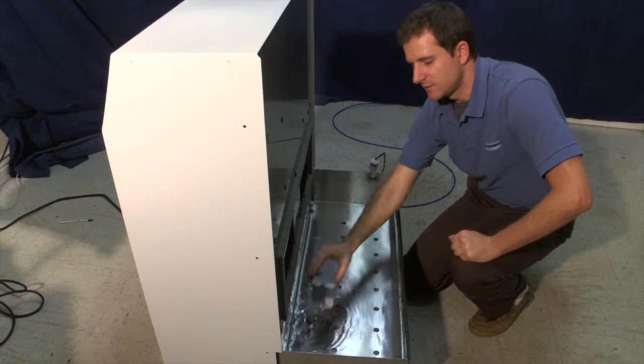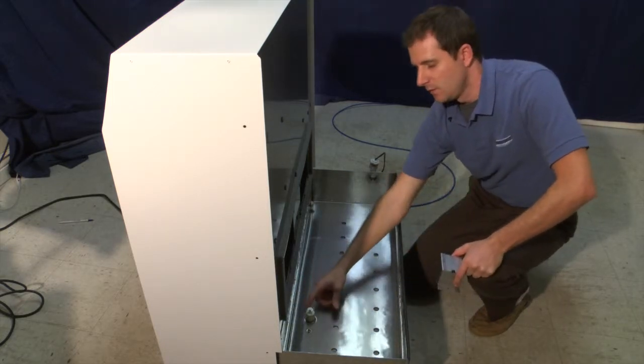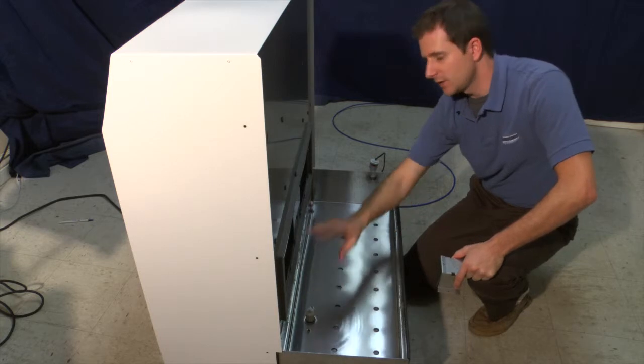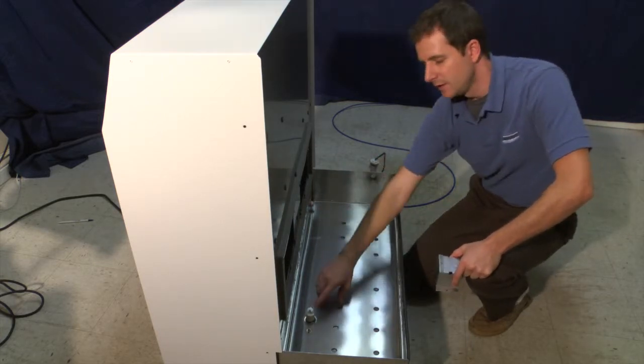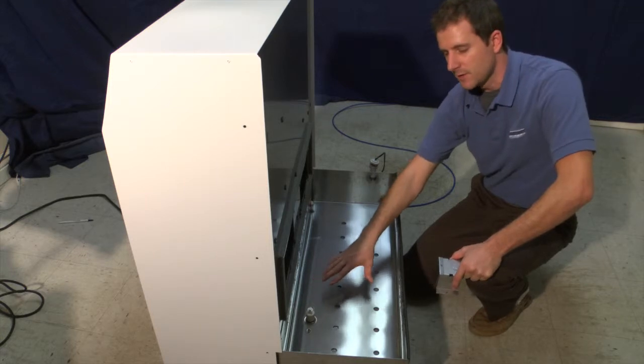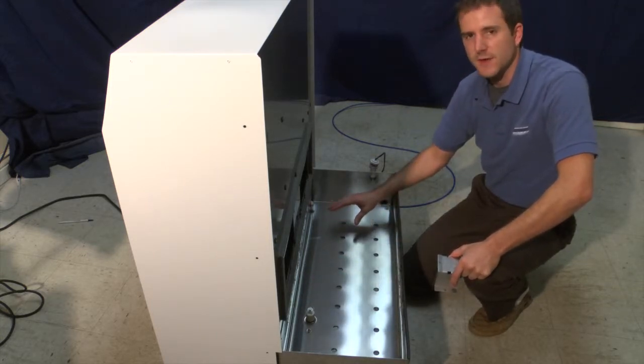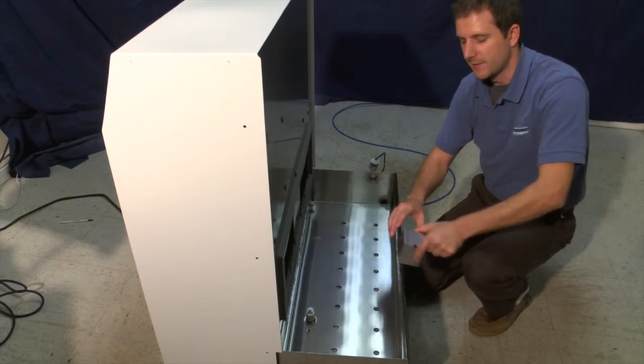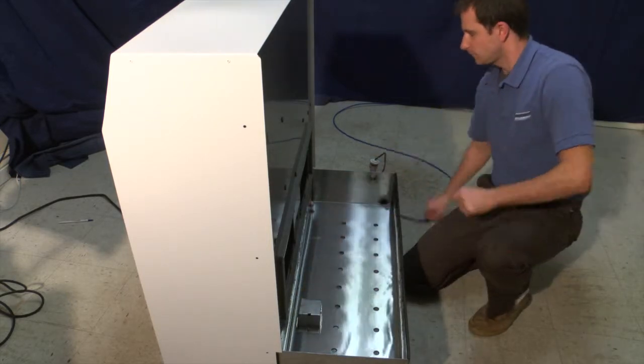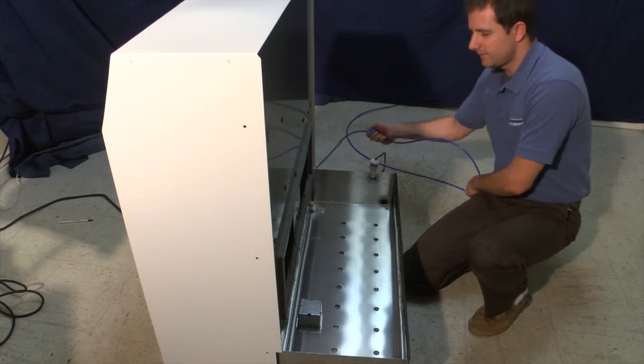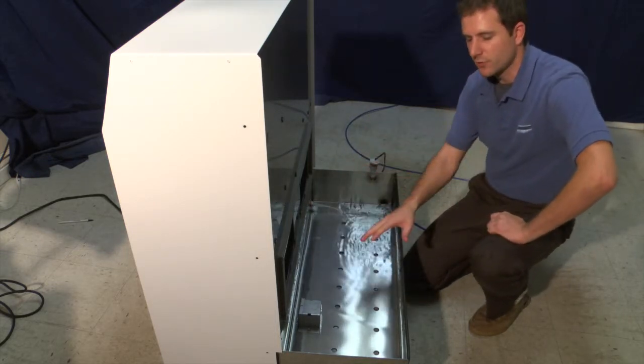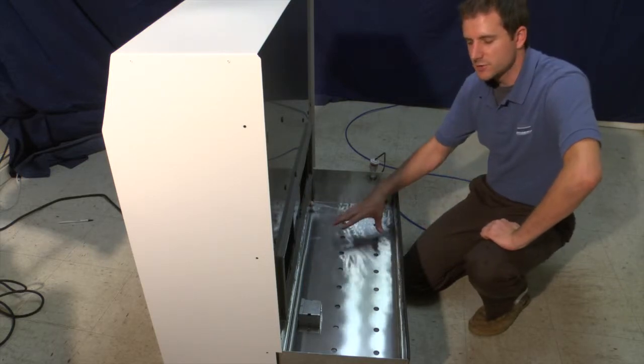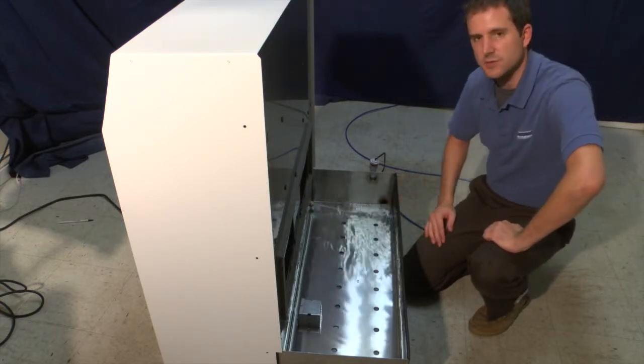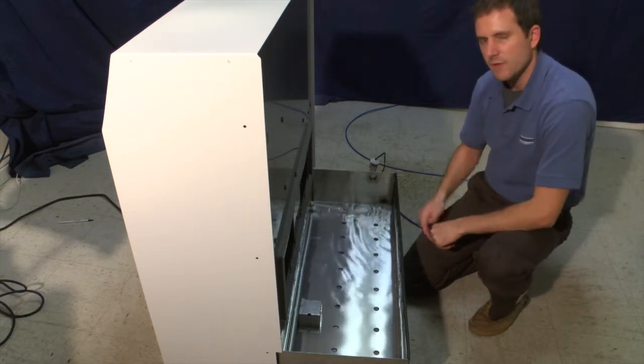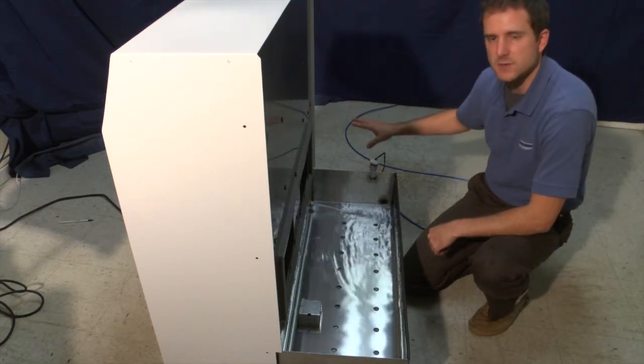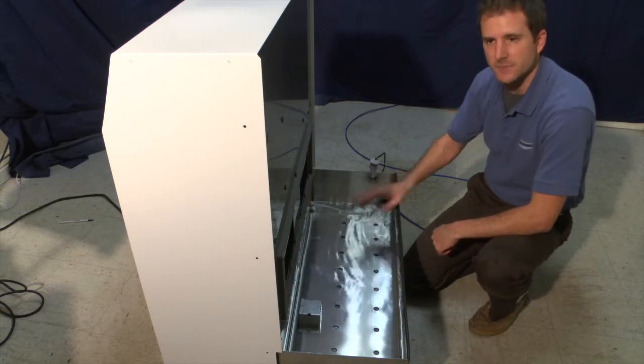Inside the small metal housing is a 2-stage float. When the float reaches a first mark, it communicates to the solenoid to refill with water. If the float hits a secondary low mark, it cuts power to the transducers so that they cannot operate without the proper amount of water on them. Activating the water line will show the humidifier refilling with water. Once the humidifier reaches the necessary amount of water, it will allow the transducers to operate again. If the water was to be shut off or interrupted, the unit would shut down completely.